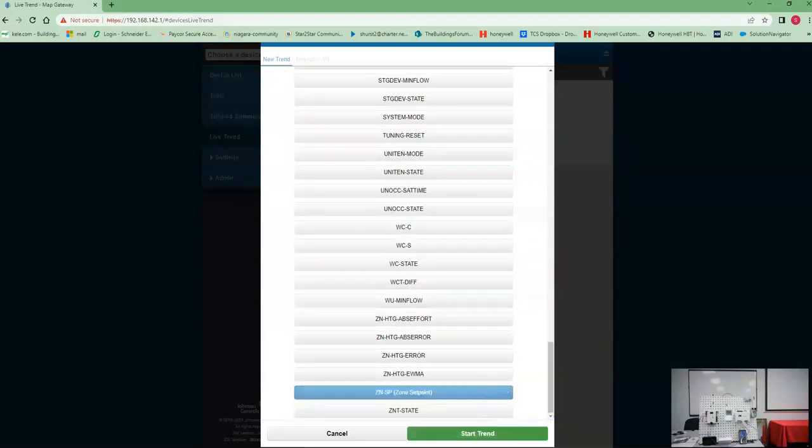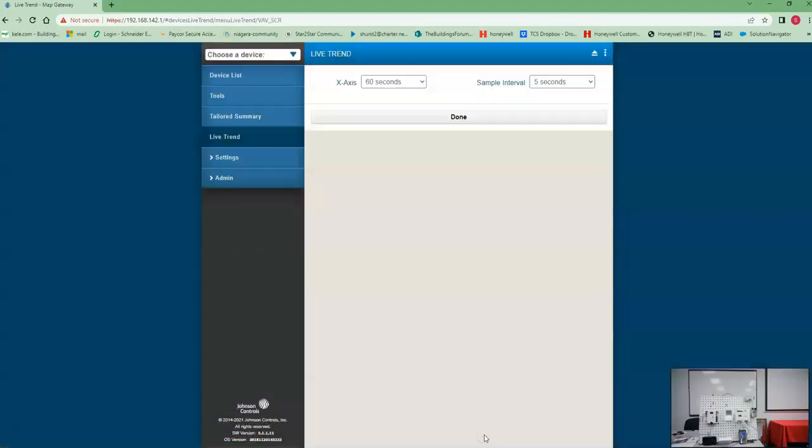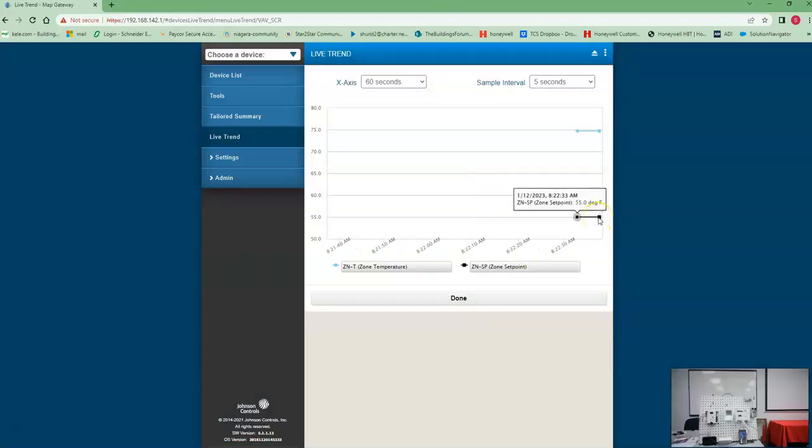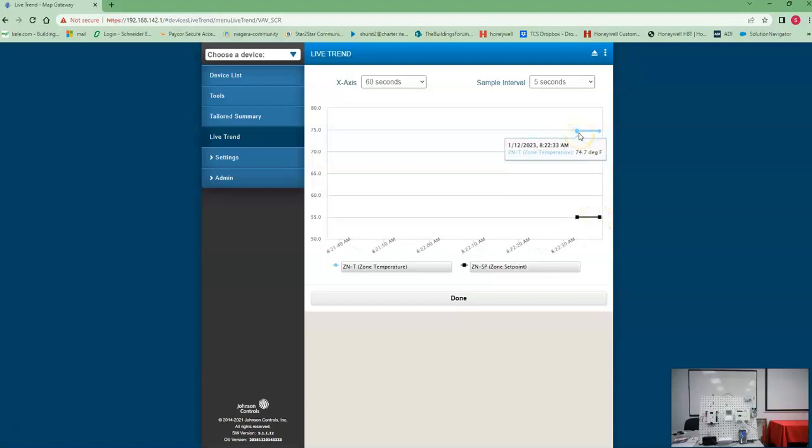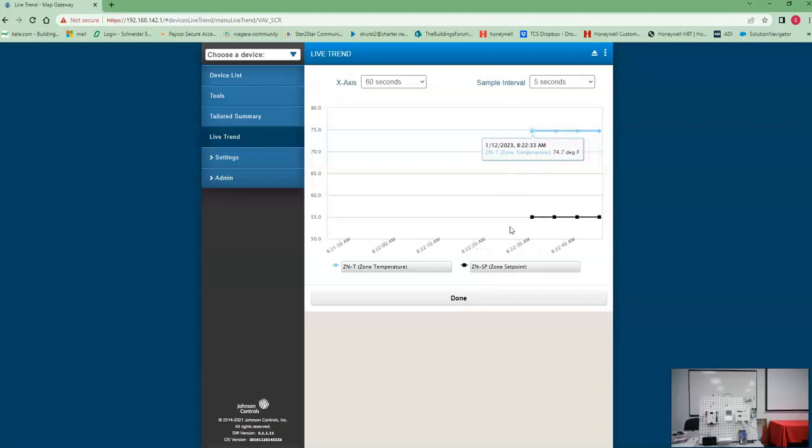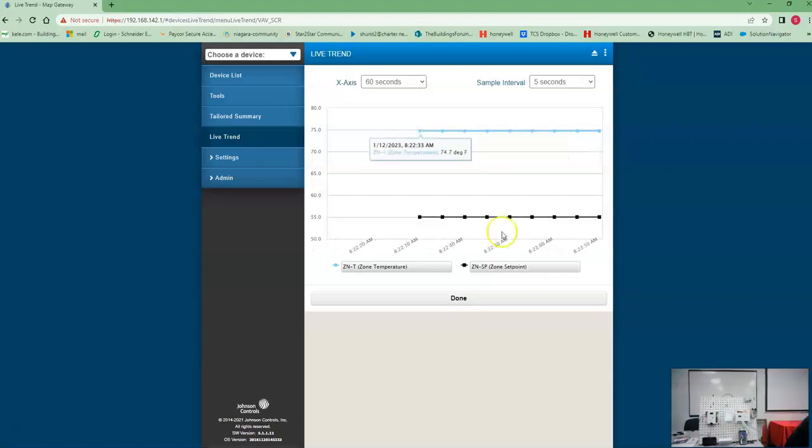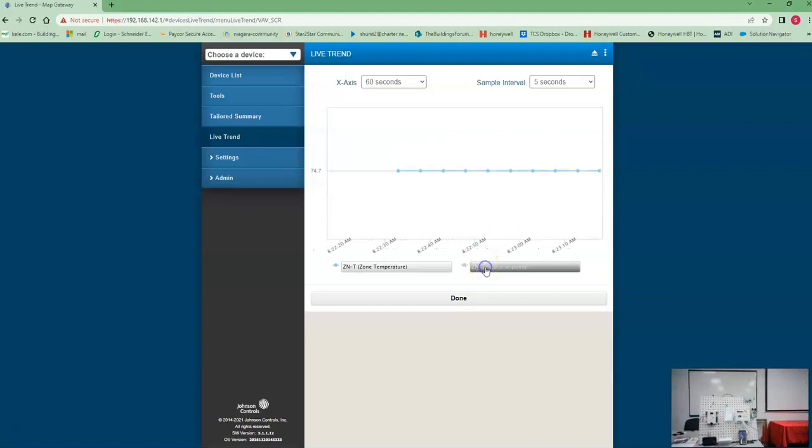Okay, start trend. So our zone set point is 55 degrees, our zone temp is 75 right here. Let's see if we can get a dip down in it or a raise up in it, something on the line that shows some movement. No movement whatsoever. What if we only do zone temp?